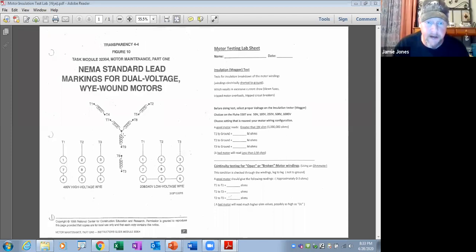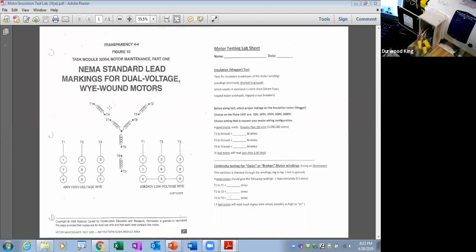It's always 7, 8, and 9. If it's a dual voltage 9-wire motor, it's always going to be 7, 8, and 9. So how can you tell if it's a Y or not with a meter? All you've got to do is this: you put an ohm meter on it, making sure the motor's unwired, like I've got right out here. Put an ohm meter on 7 and 8 and see if it rings together. If you get a low resistance reading, then ring it from 7 to 9, and then from 8 to 9, and you get a connection with all 3 of those wires. That's how you prove it's a Y wound motor, because those three wires will always be connected together, and you'll get a reading with an ohm meter.